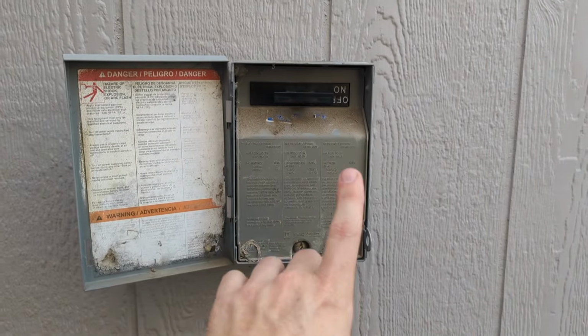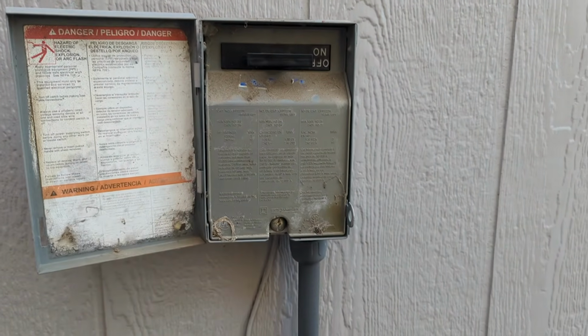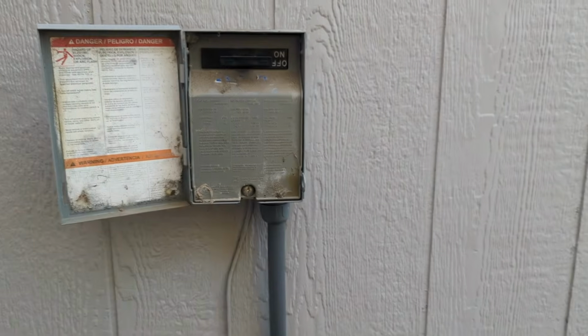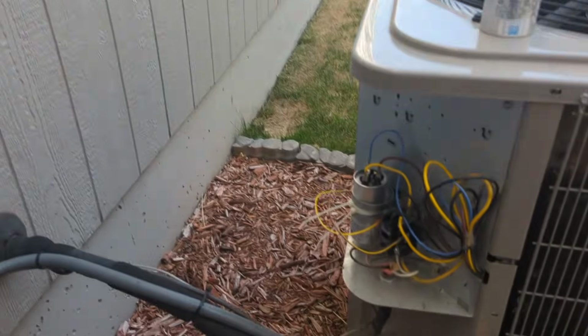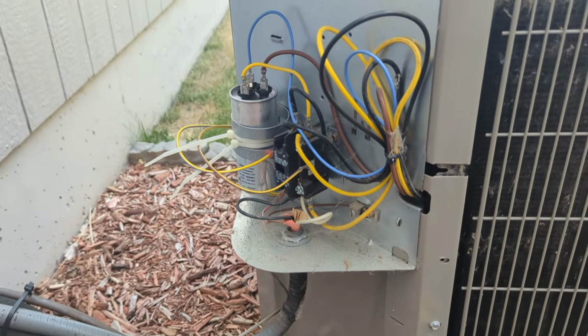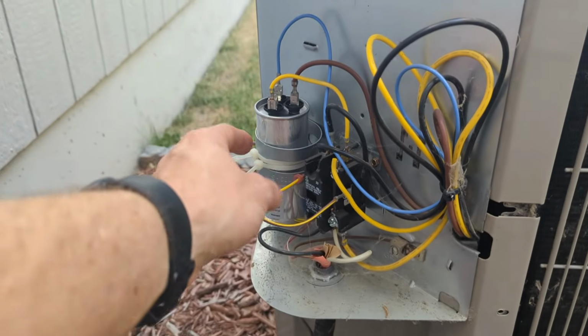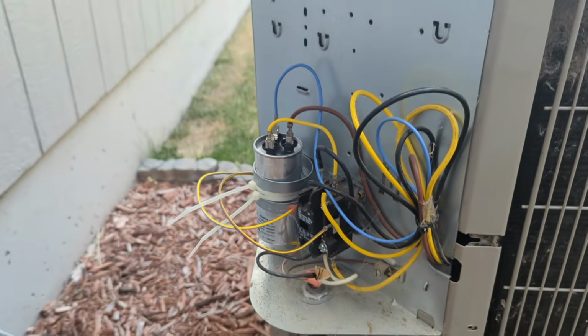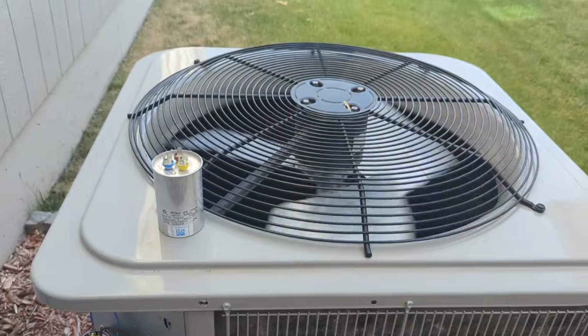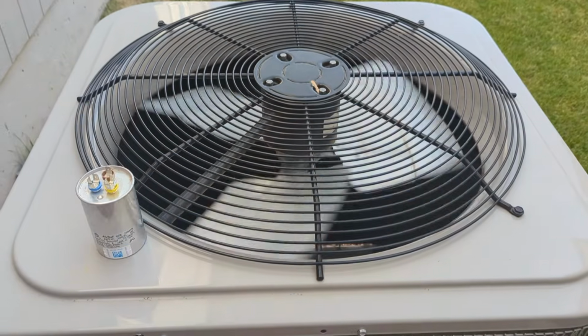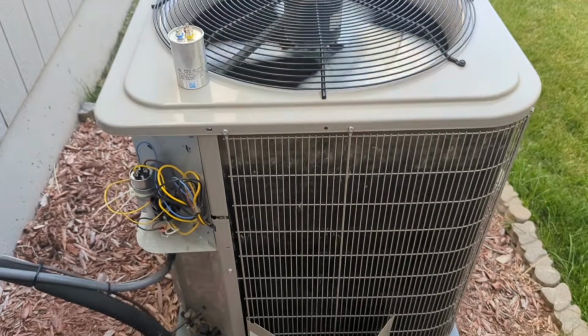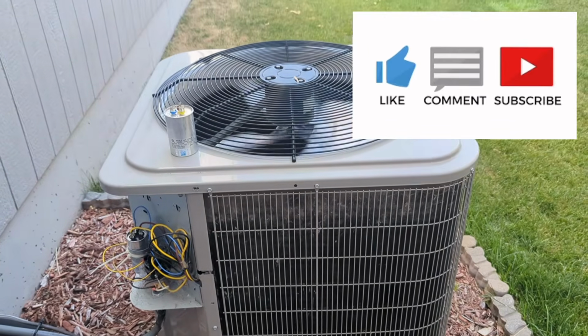All right, disconnect switch back to on. I've gone inside and turned the thermostat on and set it to cool. New capacitor is in and being held securely with these zip ties, so it's good to go. And look what we've got. A running fan. Compressor's kicked on, fan's moving, air is cooling. Another successful fix.